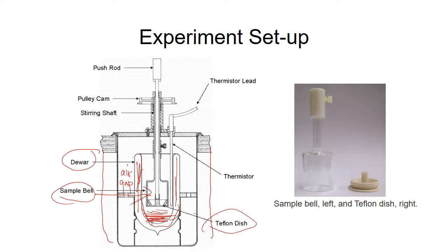If the reaction involves a solid and a liquid sample, the liquid sample is placed inside the Dewar flask and the solid is placed inside a bell-shaped sample cell. The bottom of the cell is a Teflon dish. The solid is placed inside this Teflon dish, the sample bell is then carefully pressed over this dish, and the cell is then placed inside the calorimeter.